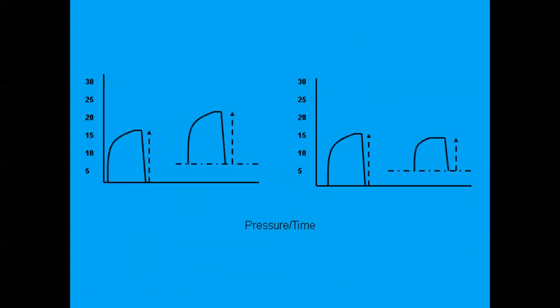So let's talk about different kinds of ventilators. You really should get familiar with the ventilators that you use where you work because they read them a couple different ways. So let's look at the one on the left here. The one on the left represents the vent like we talked about on the previous slide. This will put the set inspiratory pressure on top of PEEP. So in this scenario, if you look, we added some PEEP and it went ahead and moved the set inspiratory pressure with the PEEP. Keeps the pressure on top of the PEEP. So our pressure change or delta P remains the same on a vent like this. These are nice because whenever you make a PEEP change, it keeps your delta P. The disadvantage is that obviously if you raise the PEEP on a vent like this, your peak inspiratory pressure goes up.